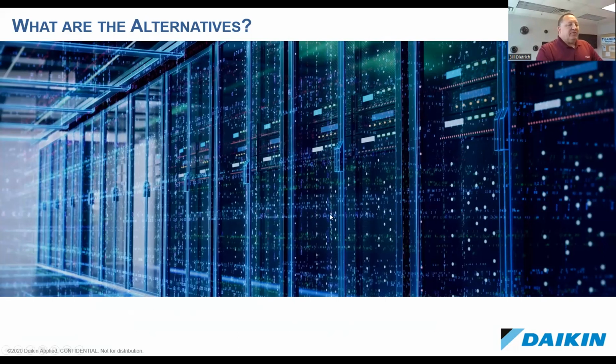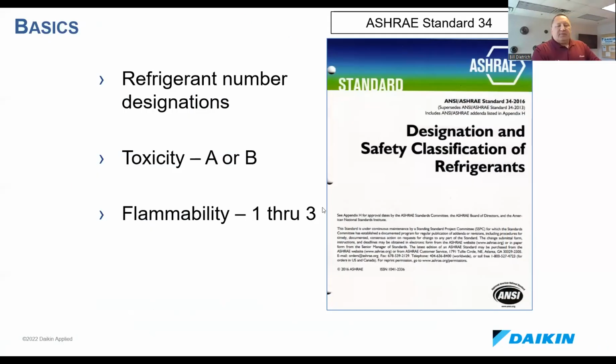So if we look at the alternatives, the first place we usually start is with some ASHRAE documentation. There's an ASHRAE committee called the Standard 34 Committee—these are the people that look at chemical compositions of refrigerants and give them their names and number designations. When we look at new compounds, they get a number designation, then a toxicity and flammability classification, which is important because that drives a lot of how these things are treated by building codes.